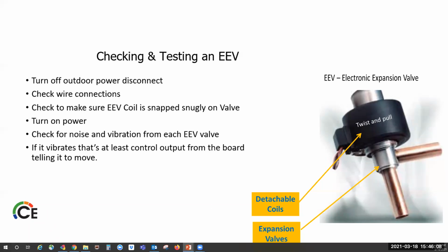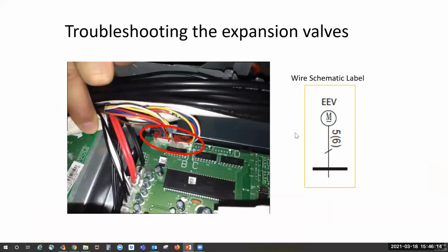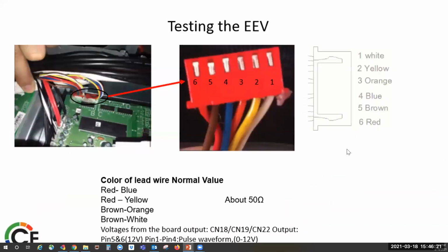You can check your voltage. We'll go over ohming it out here in just a little bit. Most of the expansion valves are either 5 or 6 wires. And when ohming out the expansion valves, you're going to check the resistance, and you're going to refer to your service manual. Most of them ohm out at 50 ohms.